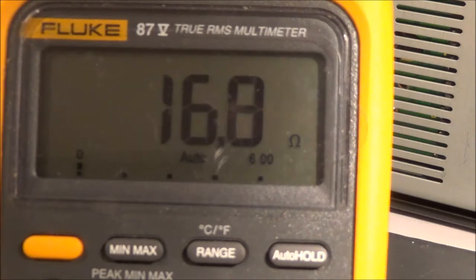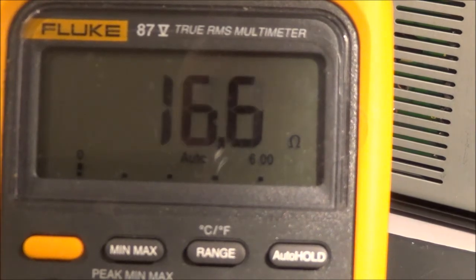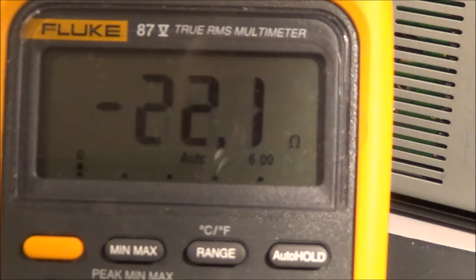I've even seen a case before where one of the brushes inside was loose, and that motor was reading basically open. Now you see I'm turning the motor by hand — it'll always go back to that low reading. I'd say a low ohm reading like this, under 20 or 20-some ohms, is about normal.